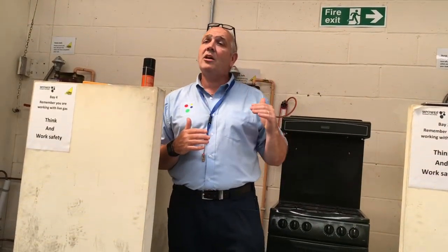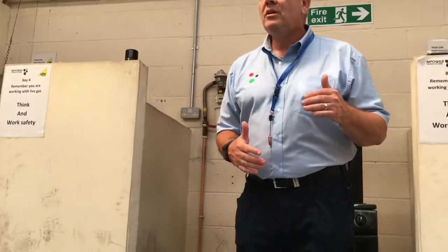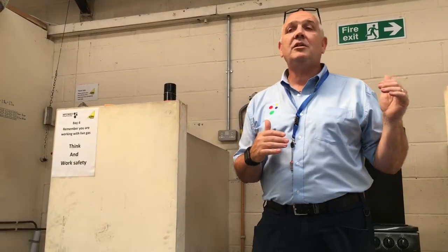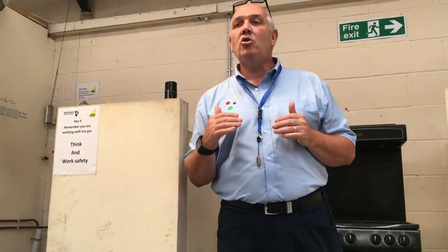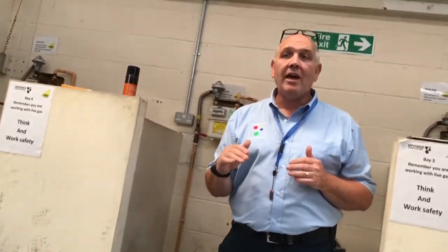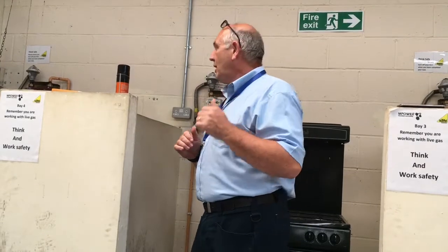And before we start, I'm going to calculate the tolerance, the upper and lower levels that we need before I even do anything. So what I need to do is 13.9 times 1.05. That will give me the upper limit. That will tell me 5% above. And then I'm going to do 13.9 times 0.9. That will give me 10% below. It won't give me 10% of it, it will show me the figure 10% below. Okay? So times it by 1.05, then times it by 0.9. When we work that out, that gives us our upper and lower limits.